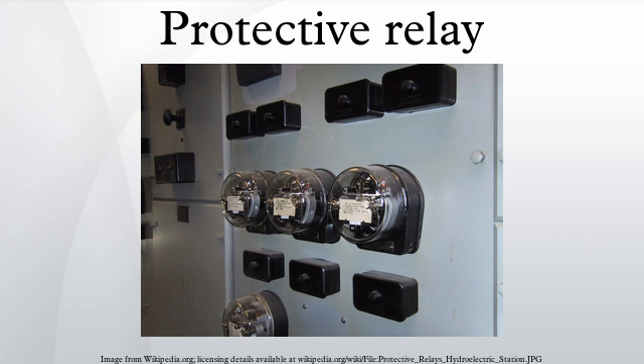By use of a permanent magnet in the magnetic circuit, a relay can be made to respond to current in one direction differently from in another. Such polarized relays are used on direct current circuits to detect, for example, reverse current into a generator. These relays can be made bistable, maintaining a contact closed with no coil current and requiring reverse current to reset. For AC circuits, the principle is extended with a polarizing winding connected to a reference voltage source. Lightweight contacts make for sensitive relays that operate quickly, but small contacts can't carry or break heavy currents. Often the measuring relay will trigger auxiliary telephone-type armature relays.